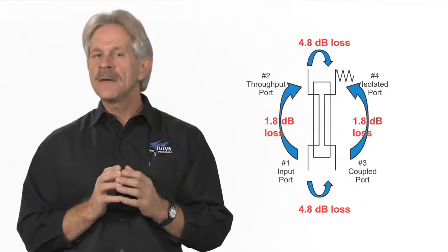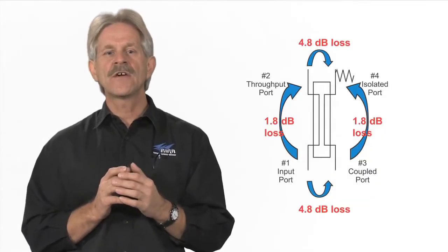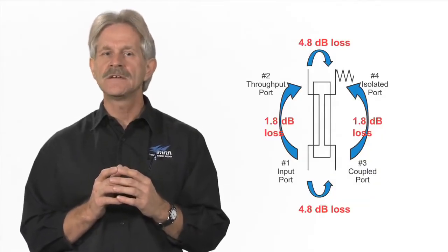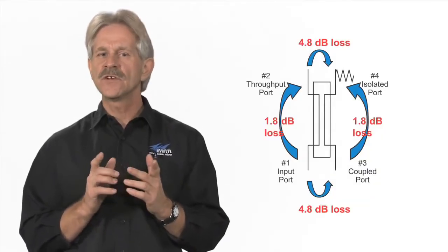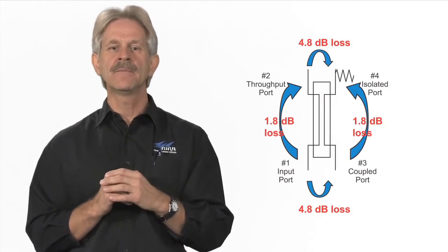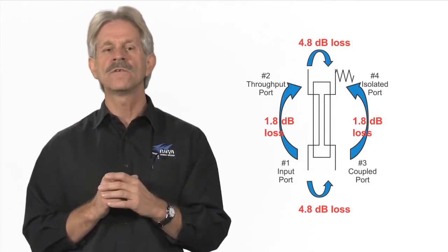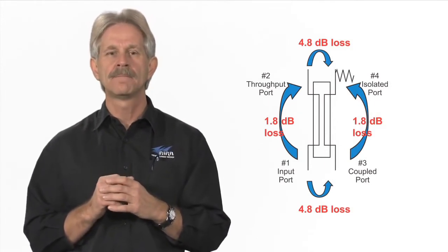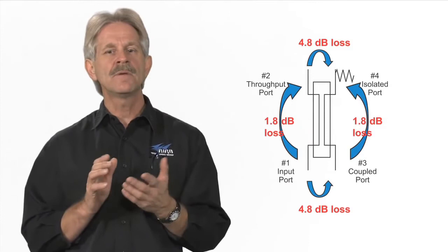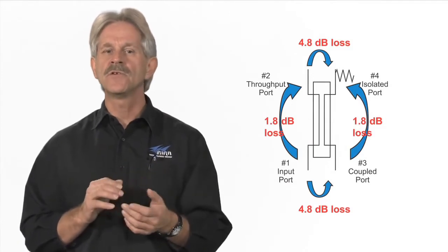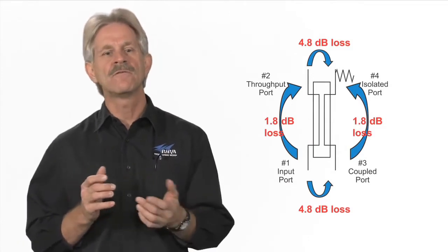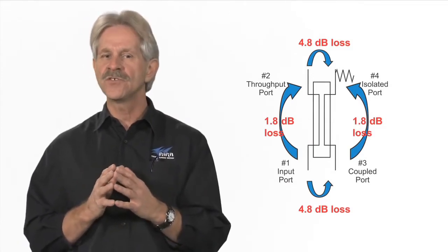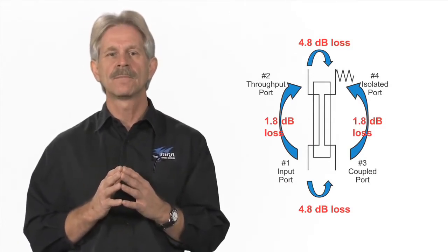To maintain satisfactory signal-to-noise ratios in a DAS, the signal loss at any antenna should be limited to no more than 25 to 30 dB. This can be accomplished by using the appropriate four-port directional couplers instead of splitters.